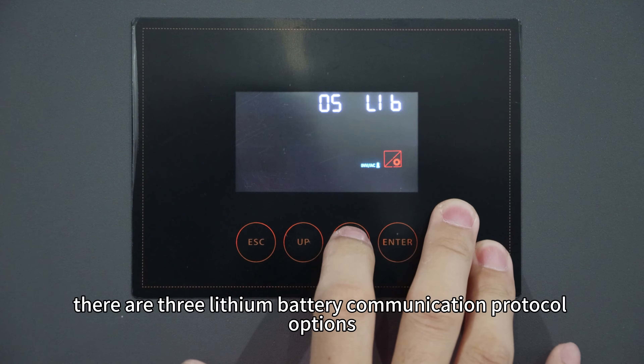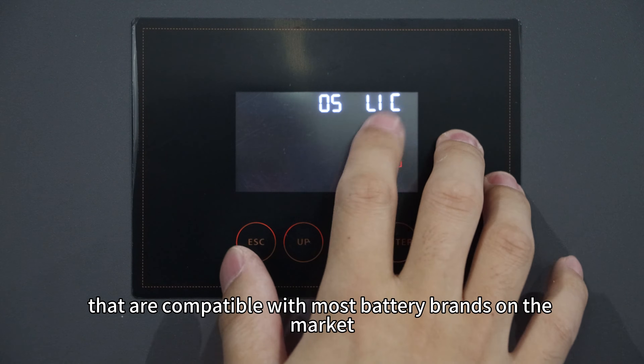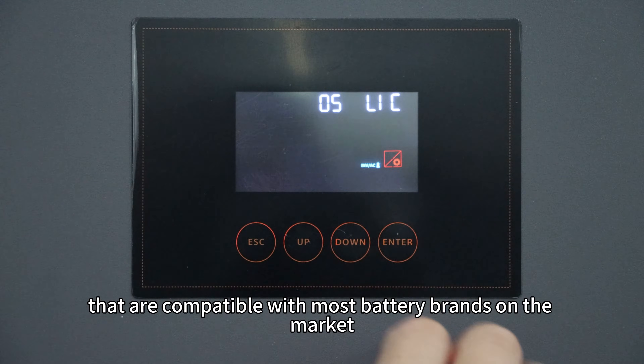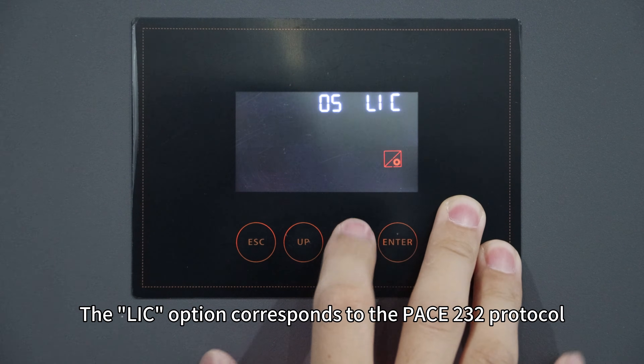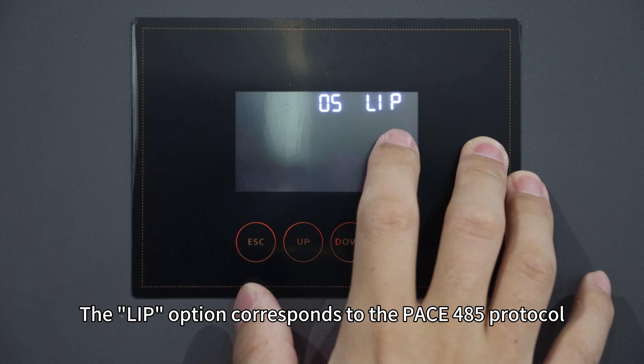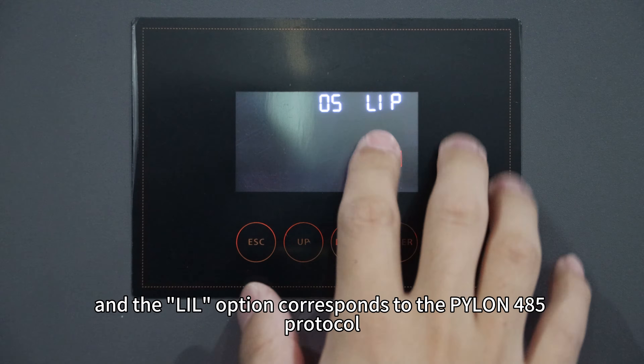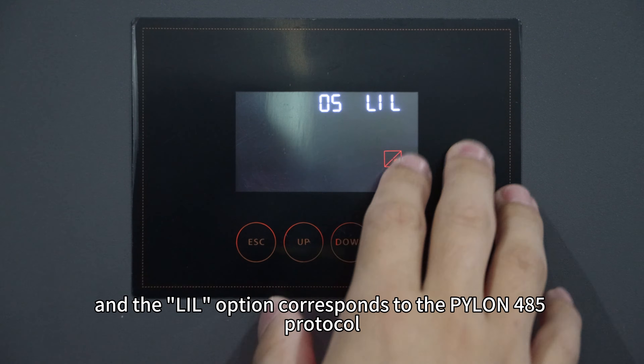There are three lithium battery communication protocol options compatible with most battery brands on the market. The LIC option corresponds to the PACE 232 protocol. The LIP option corresponds to the PACE 485 protocol. And the LIL option corresponds to the PYLON 485 protocol.